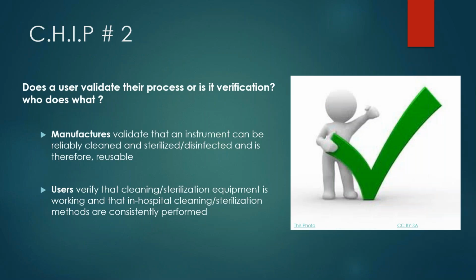CHIP tip number two: does a user validate their process or is it verification? Who does what? Well, we do get this question quite a bit, and manufacturers are the ones that validate an instrument that can be reliably cleaned and sterilized and disinfected and therefore reusable. The user is responsible for verifying that cleaning and sterilization equipment is working and that in-hospital cleaning and sterilization methods are consistently being performed.